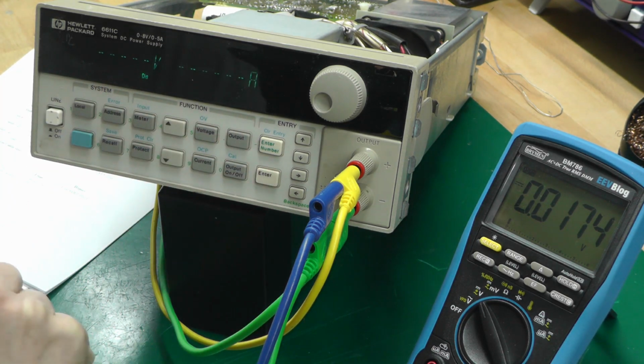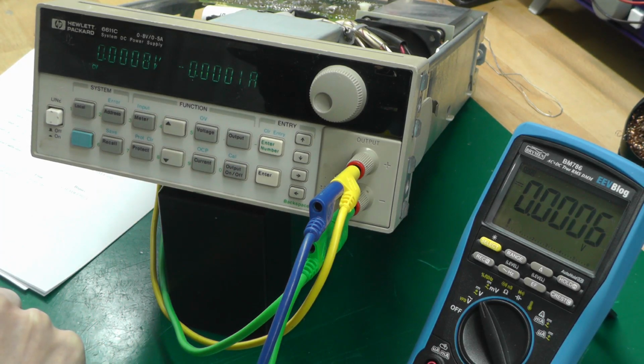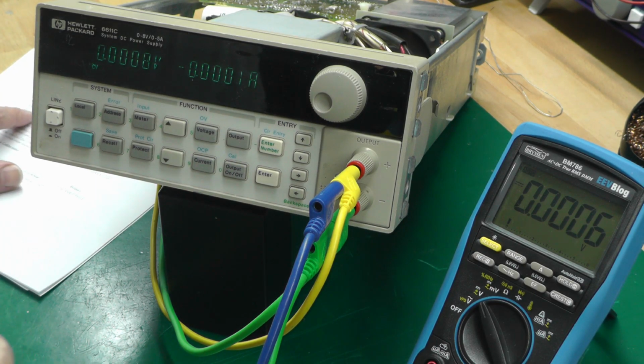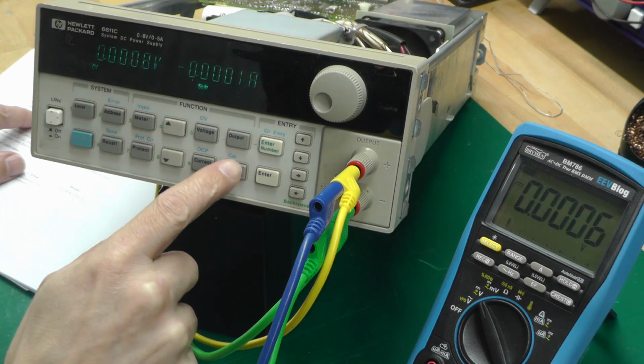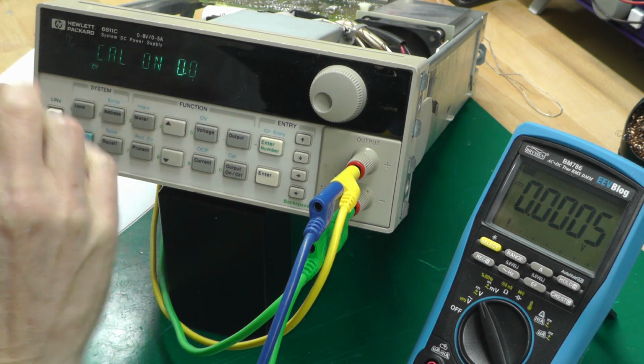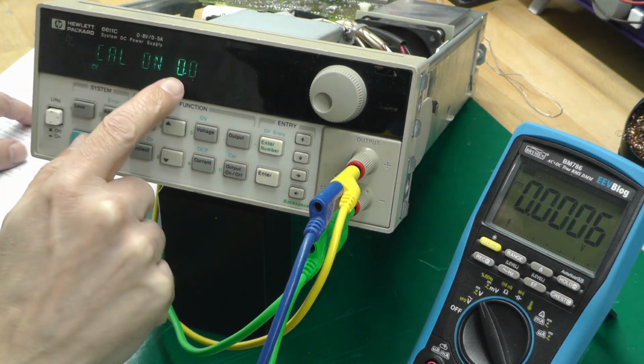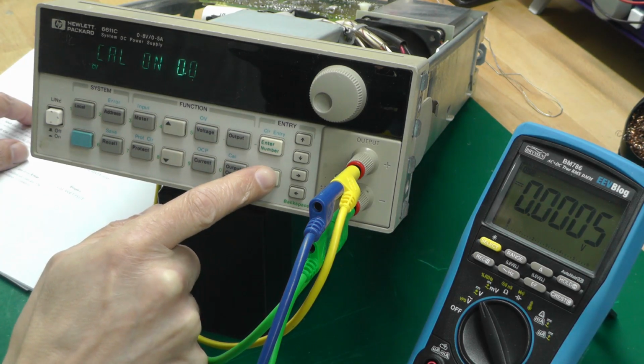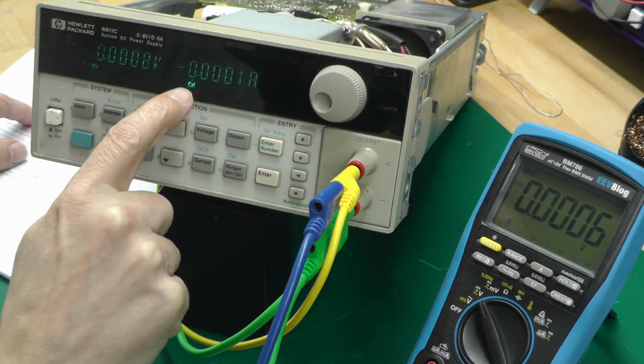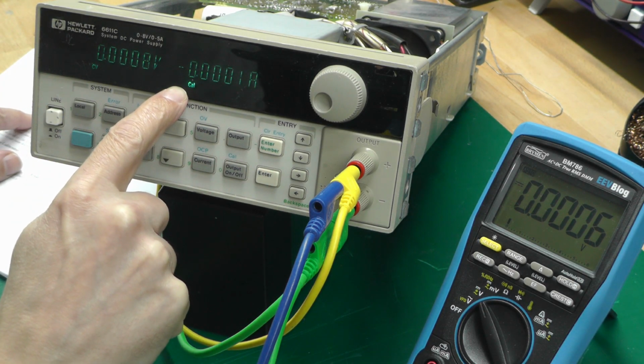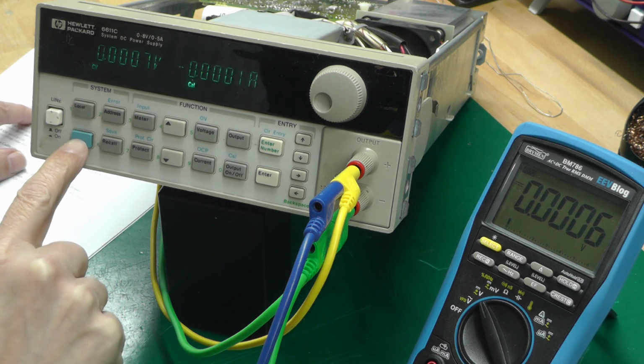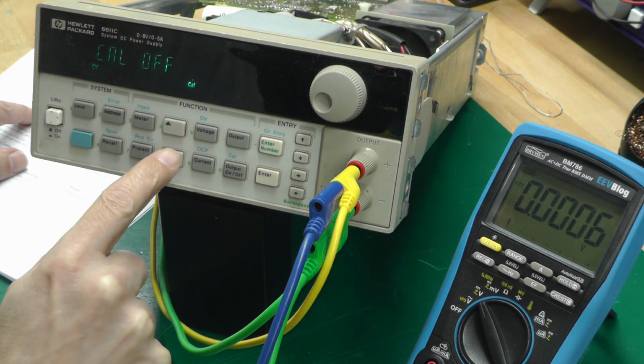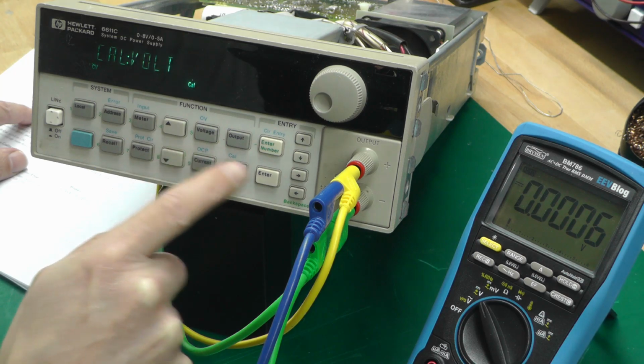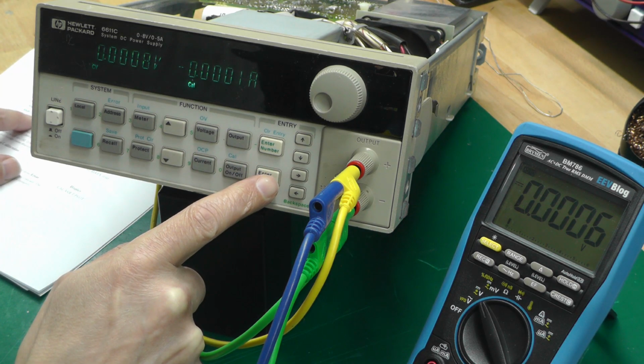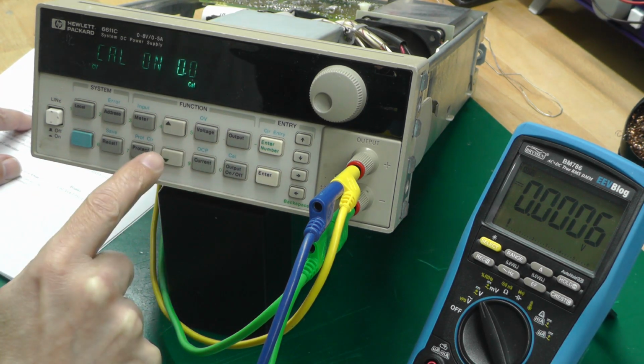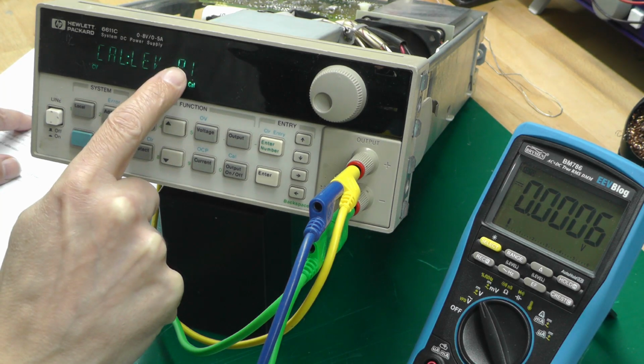So that's that reset, turn the output on and press Shift Cal. It's asking for a password. The default is 0. It's like a 2-digit number. It's 0 at the moment, so press that. So I'm into calibration mode, which is signified by the CAL. So now I'll go to Shift Cal, go to Cal Volt. There we go, press enter, and then Shift Cal again, go to Cal Lev P1.